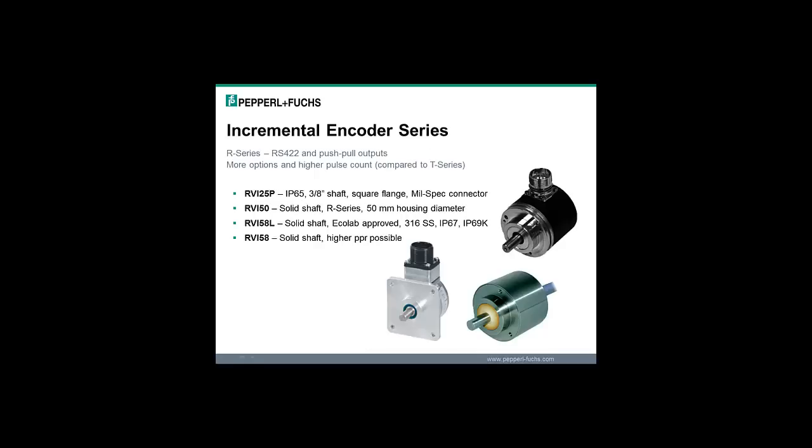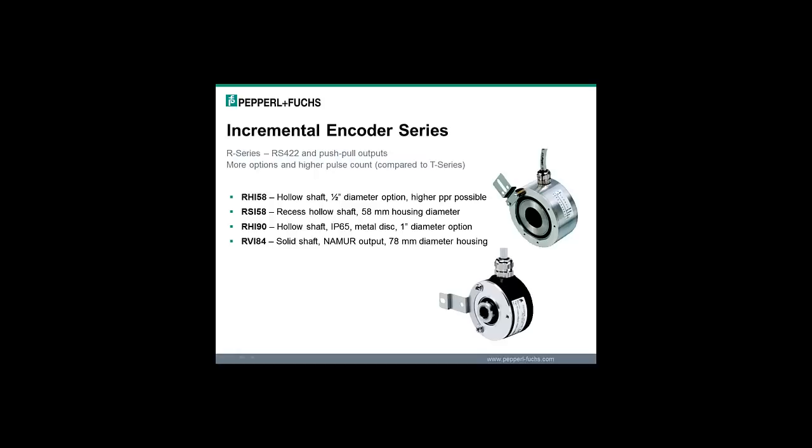The R-series has more options with higher pulses per revolution, up to 50,000. In the R-series, the RHI-58 has a hollow shaft with a half inch diameter option and higher pulses per revolution is possible. The RSI-58 is a recessed hollow shaft with a 58 millimeter diameter housing. The RHI-90, hollow shaft with a one inch diameter option. And the RVI-84 is a solid shaft with an NAMUR output and a 78 millimeter diameter housing.